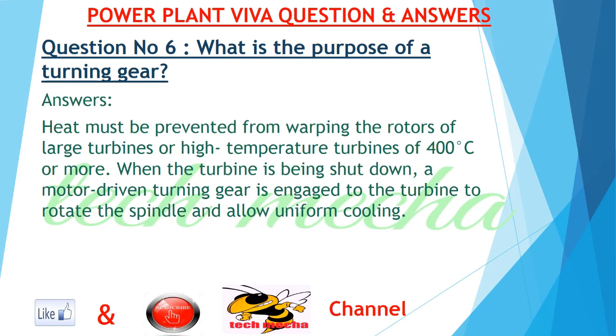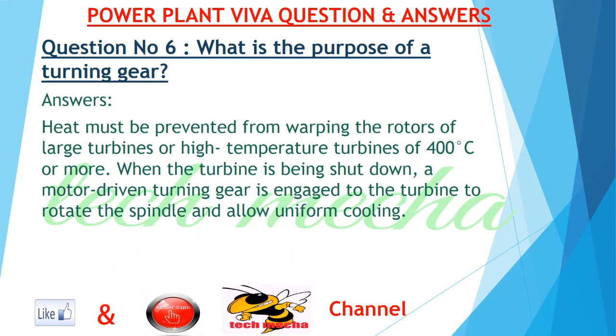Question number 6: What is the purpose of a turning gear? Answer: Heat must be prevented from warping the rotors of large turbines, or high-temperature turbines of 400 degrees centigrade or more. When the turbine is being shut down, a motor-driven turning gear is engaged to the turbine to rotate the spindle and allow uniform cooling.